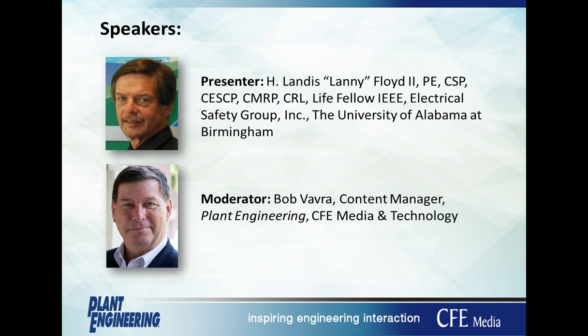What is becoming more common today is high resistance grounding, which can be done on center grounded Y systems. On some of them there are issues you have to avoid around line to ground loads. Going to the question on the Delta grounded or Delta 480 volt systems, there is some technology you can use to create a grounding point for those Delta systems. I would work closely with a knowledgeable supplier, either the manufacturer of switchgear and equipment, or engineering services competent in industrial power system design. There are solutions to that issue that can improve safety and reliability.